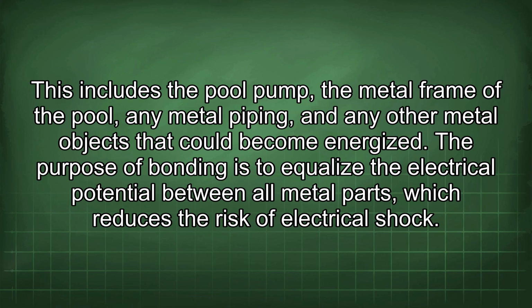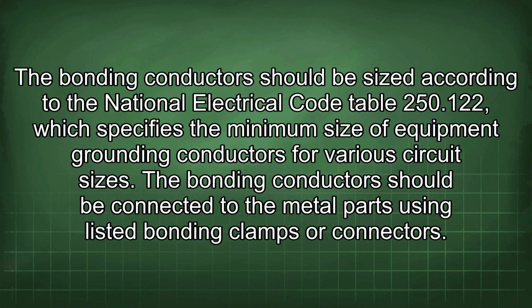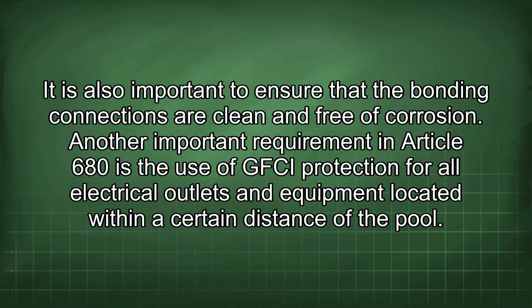The purpose of bonding is to equalize the electrical potential between all metal parts, which reduces the risk of electrical shock. The bonding conductors should be sized according to the National Electrical Code Table 250.122, which specifies the minimum size of equipment grounding conductors for various circuit sizes. The bonding conductors should be connected to the metal parts using listed bonding clamps or connectors. It is also important to ensure that the bonding connections are clean and free of corrosion.